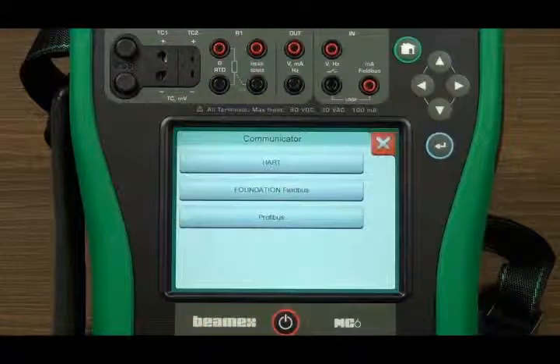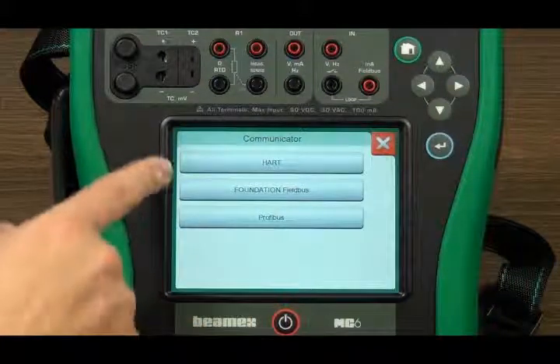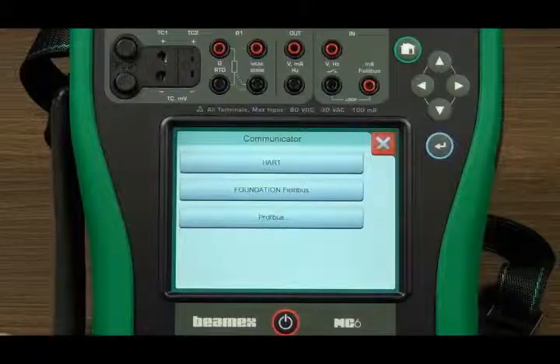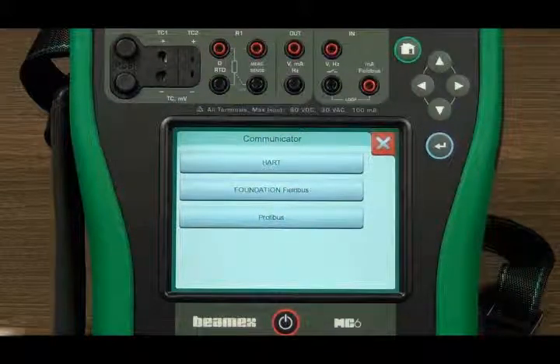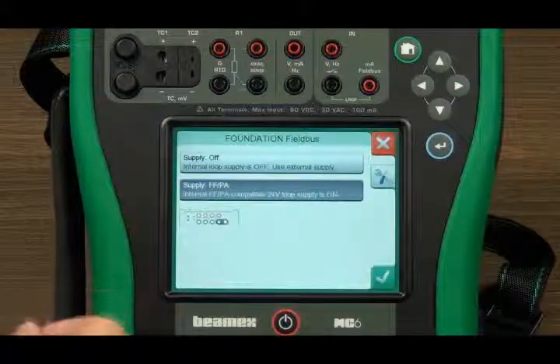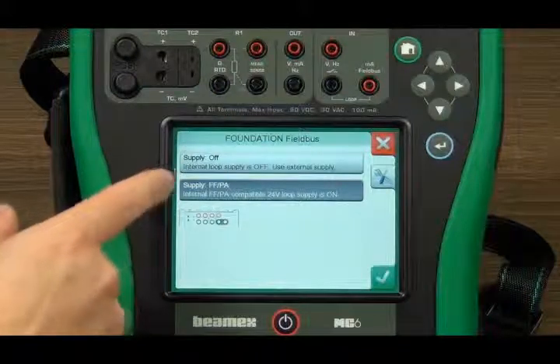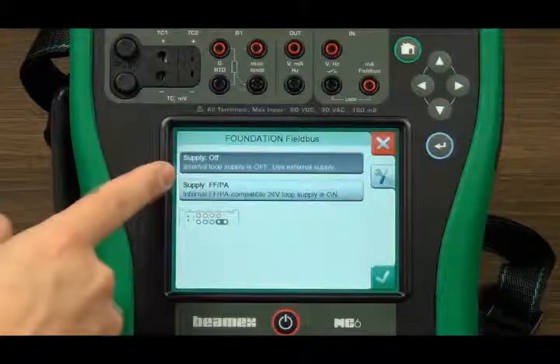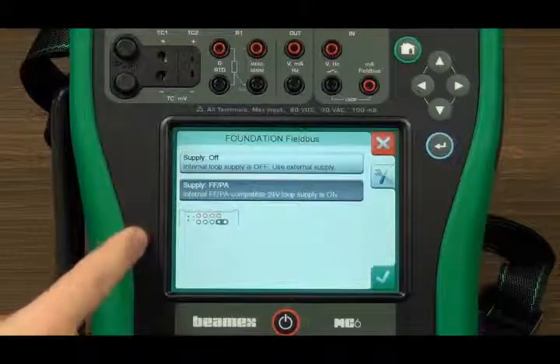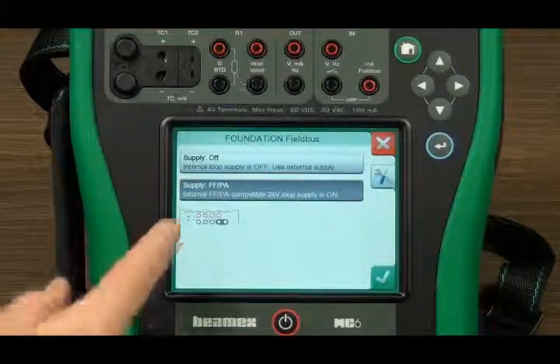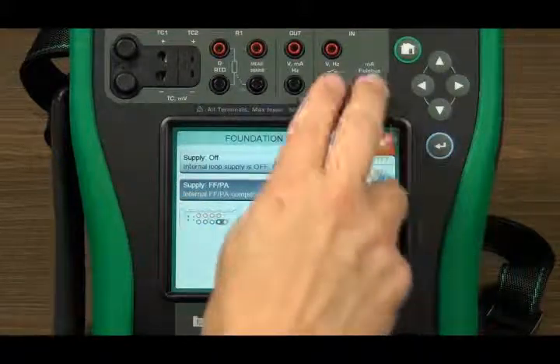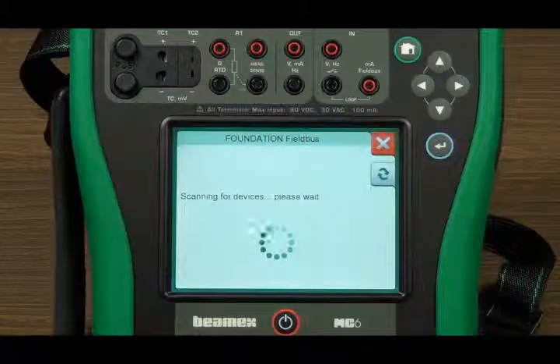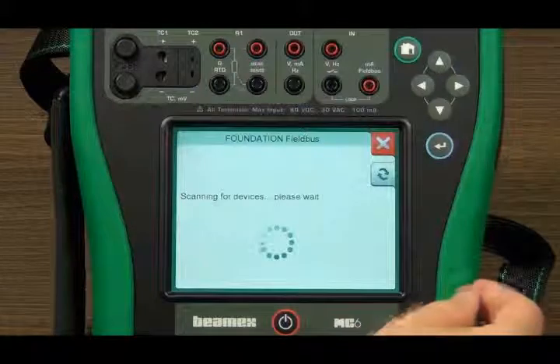Communicator. The communicator mode is a full field communicator for HART, Foundation Fieldbus and Profibus PA instruments. First you select the required protocol. Then select either the internal Fieldbus compatible power supply or an external supply. The connection diagram shows you where to make the connections. Touch the green tick to start polling the selected protocol. Now, connect your Fieldbus instrument and proceed.